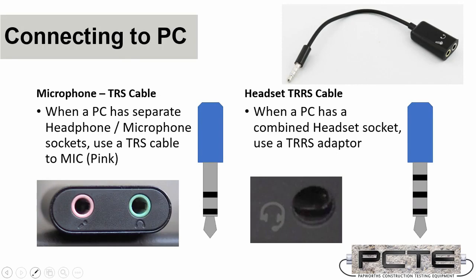So to use the concrete thickness gauge, it needs to be connected to the PC. And this is done through the sound system of that PC. So the first thing is to know what's the correct port to plug that into, and what the right cable is. There's two kinds of common ports which you can plug a microphone into, and it'll depend which one your PC has.